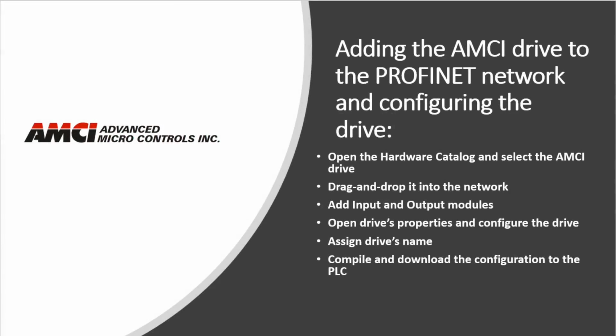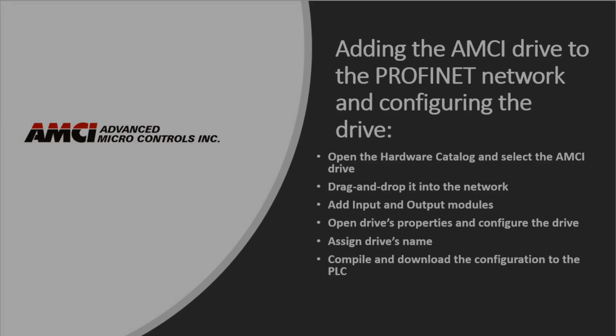After the GSDML file is installed, the AMCI drives will appear in the hardware catalog. So we're going to open the hardware catalog, find and select the AMCI drive, drag and drop it into the network, add input and output modules, open the drive's properties and configure the drive, assign the drive's name, and as a last step, we're going to compile and download the configuration to the PLC.